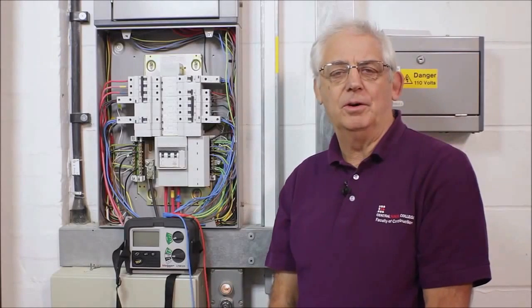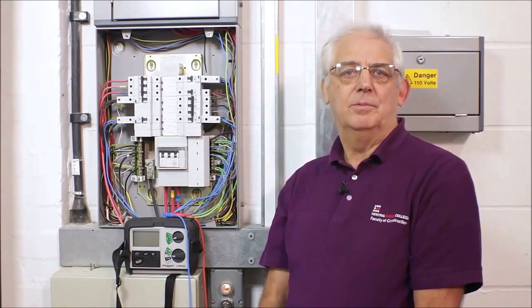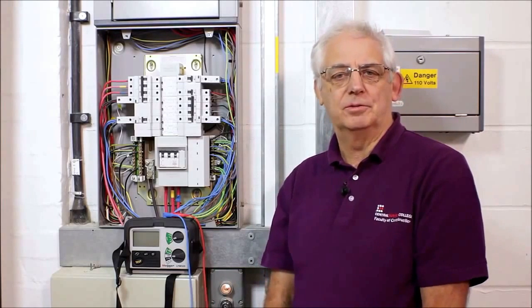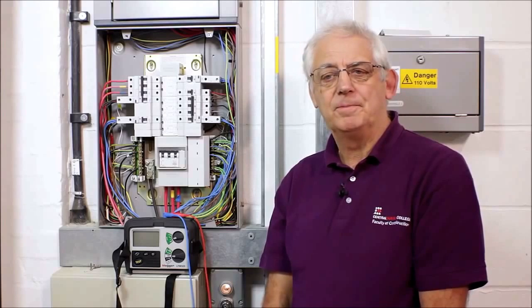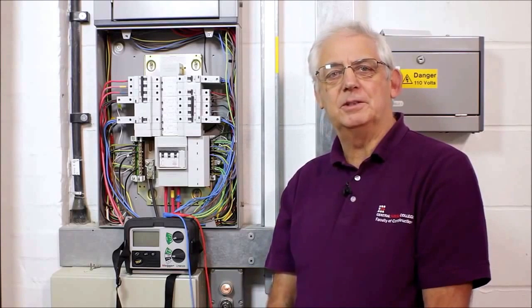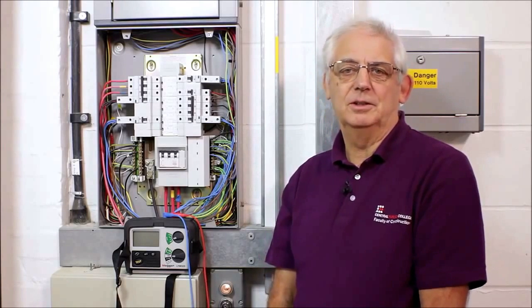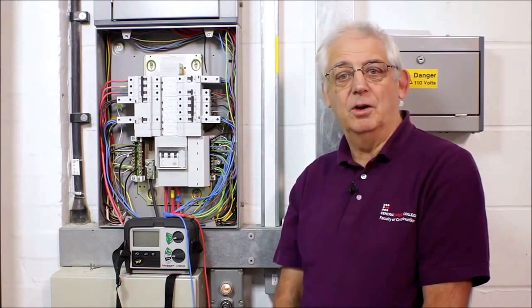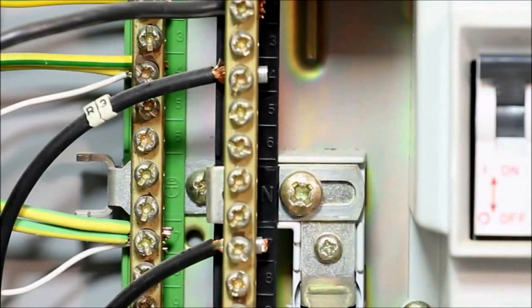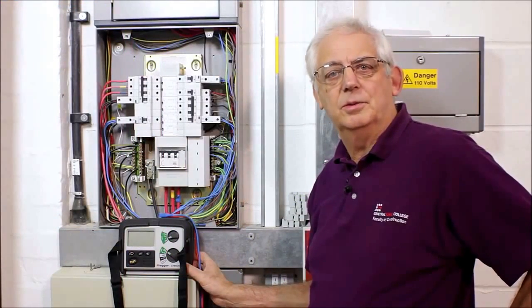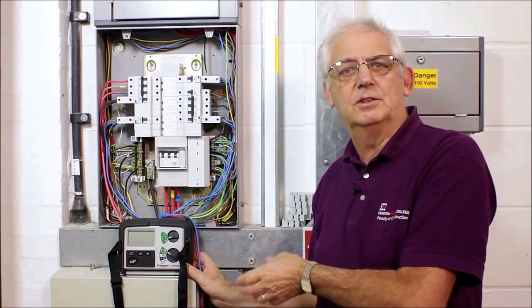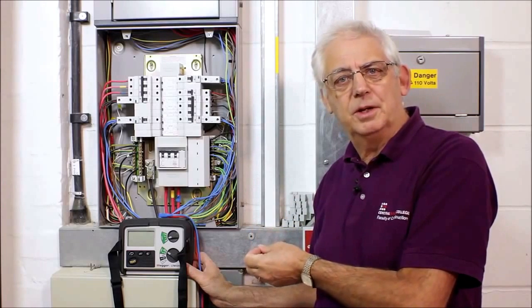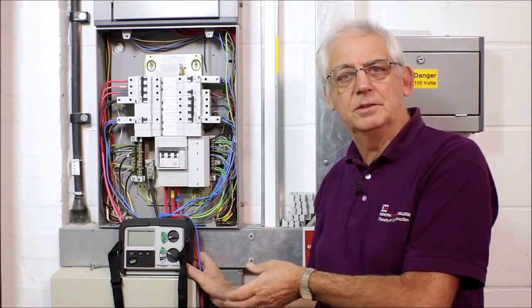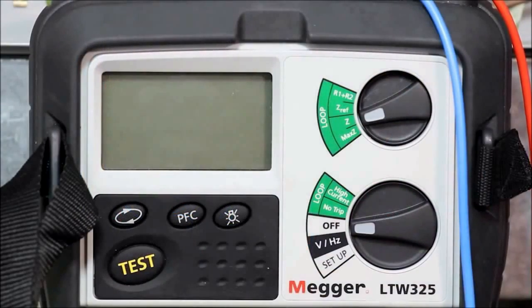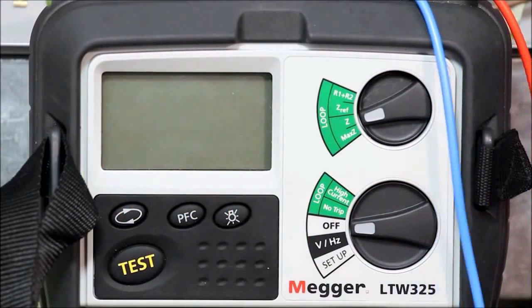It's a requirement of our wiring regulations that any equipment must be able to withstand the maximum current that could flow where it's installed. So for that, we need to find the prospective fault current, which is obviously known as PFC, sometimes known as Ipf. That's the maximum current that can flow. Because we need to measure the highest value that's likely to flow, we need to make sure that everything is connected and turned on, because that way at least we'll get current flowing through all of the parallel paths. That's quite important. For that, I need to use a prospective fault current tester.